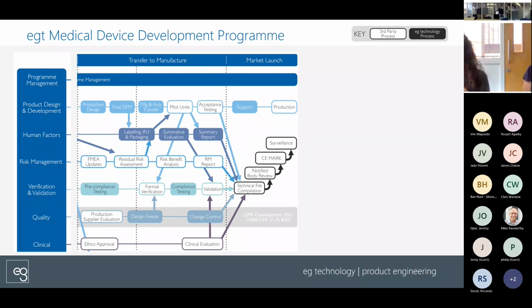That all then gets wrapped up in a report with all of your usability engineering files, which contribute towards your technical file. And as you can see, there are lots of other things that are all feeding into that technical file as well. Your other acceptance testing, compliance testing, formal verification testing of your product, as well as, of course, the clinical evaluation, which, as I said, needs to happen after summative evaluation, and that's your final validation step. And all of your quality management and final risk management steps, your risk benefit analysis, all of this needs to feed into your technical file before you go to notified body review and hopefully launch your product.